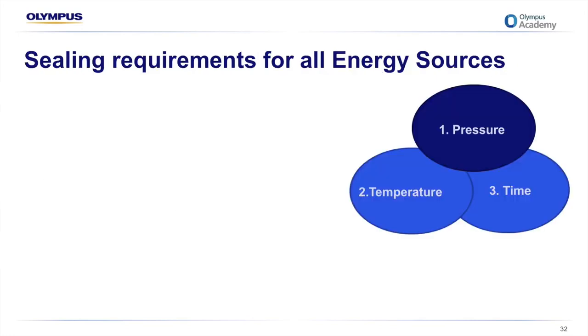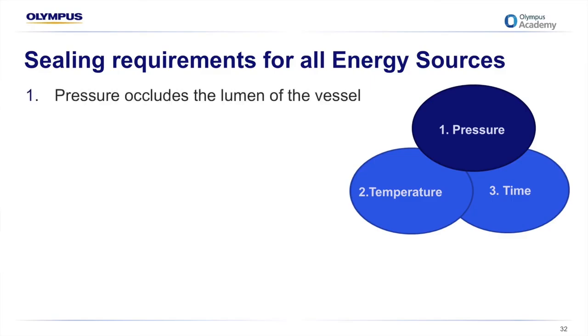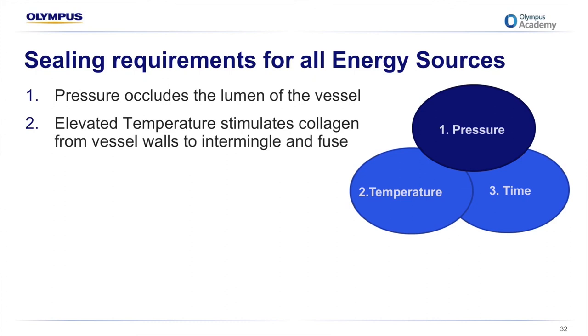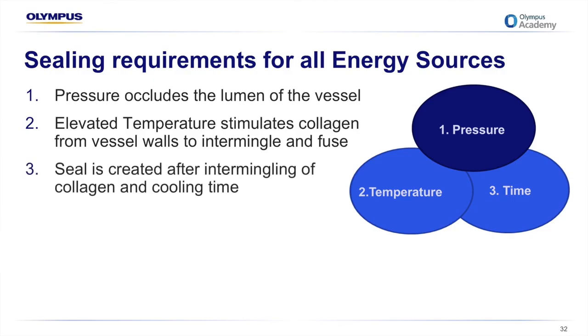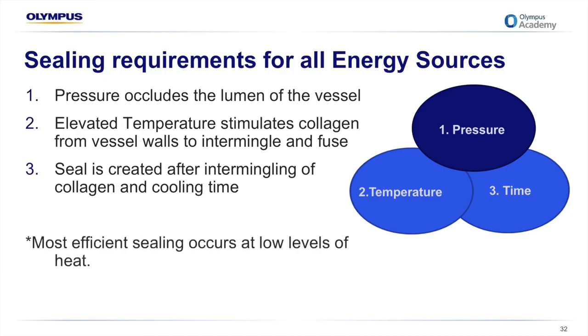And whilst we're talking about sealing vessels, there are 3 requirements of all energy sources that are needed in order to provide a reliable seal of a vessel. Namely, pressure, which occludes the lumen of the vessel, an elevated or increased temperature, which stimulates collagen from vessel walls to intermingle and fuse, and then the seal is created after this intermingling of the collagen and a reliable cooling time. Remembering, most efficient sealing occurs at low levels of heat.